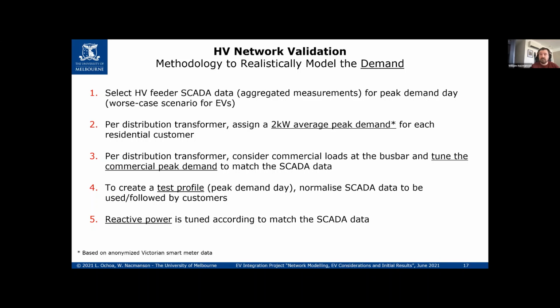So then we look at the difference between the demand with just the residential load that we do know, because we know the number of customers, and the measured demand, which we get from the SCADA data at the head of the feeder. And then we tune the load of the commercial customers, which are spread across the different distribution transformers, until we match the data from the SCADA.